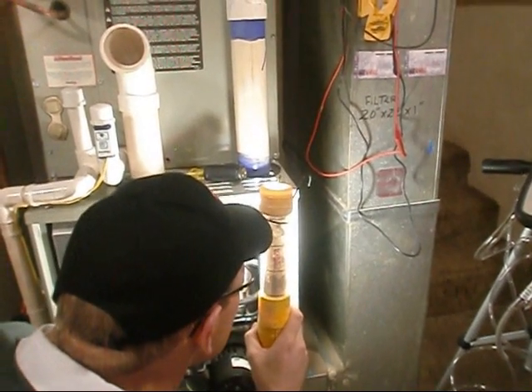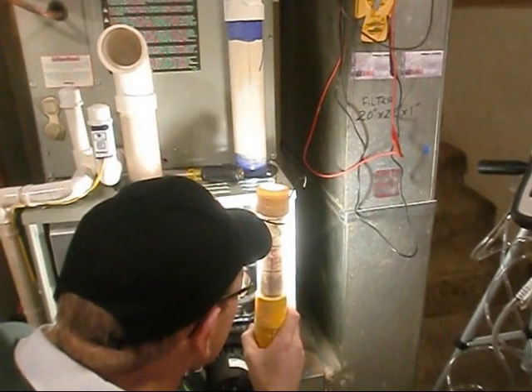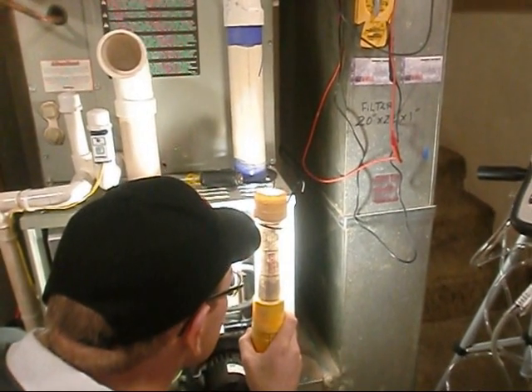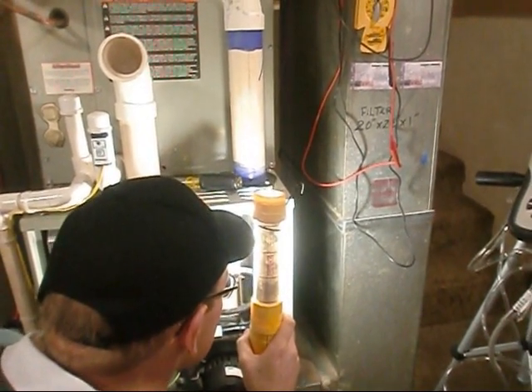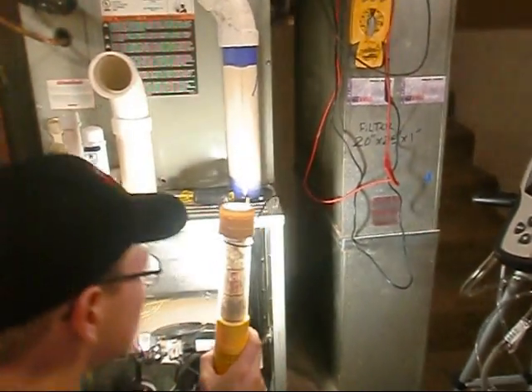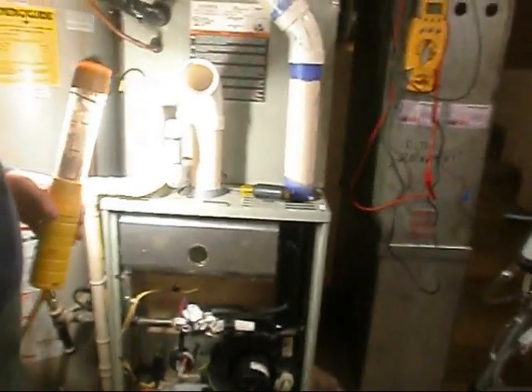Okay, there it is. It'll be pretty close to that last one you found. Hourly input 80,000 BTU. That's it, at 3.5 inches water column. Yes, sir, that's what we're looking for. That's according to the manufacturer's specs.